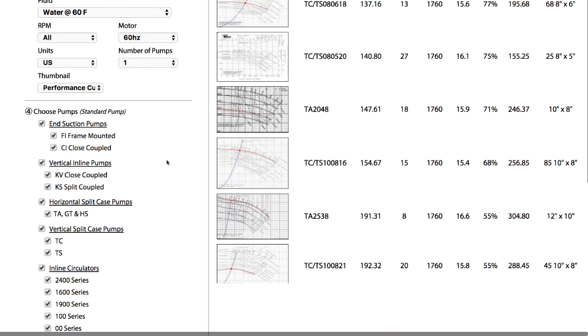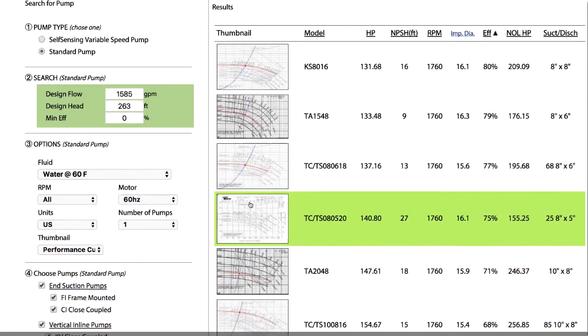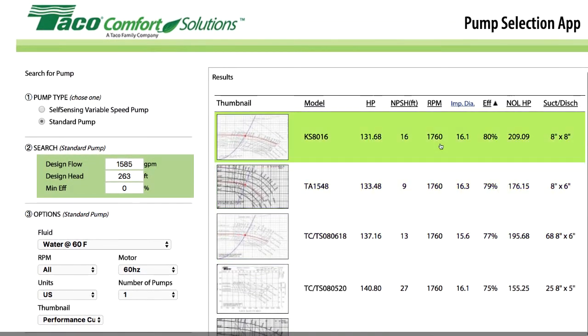I've got a variety of different pumps here with pump curves. This model KS-8016 is going to need about 130 horsepower — a fairly big pump. It has an NPSH of 16 feet, operates at 1,760 RPM with a standard electric motor drive, an impeller diameter of about 16 inches, efficiency about 80 percent, and both suction and discharge lines are eight inch. We were designing with six inch piping, so the eight inch lines suggest we may have gone a little undersized.